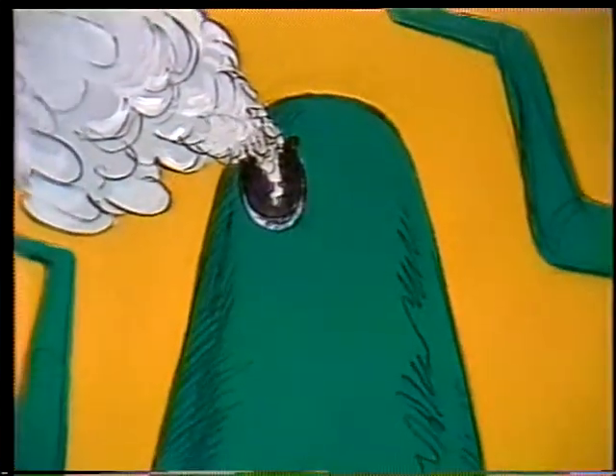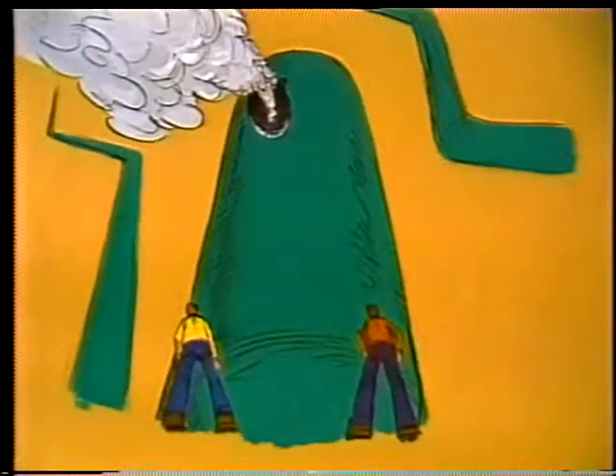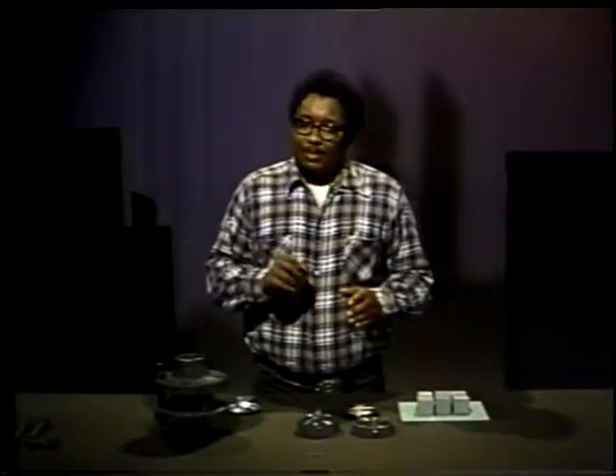No matter what type of rupture disc is used, the principle is the same. The disc forms a weak spot in the system, saving other parts of the system from pressure damage. And if a rupture disc is placed well away from heavily traveled areas and normal work areas, it also relieves excess pressure safely, away from workers and other equipment. If a rupture disc must be used where workers normally are, it can be connected to discharge piping, which will safely carry the pressurized fluid away when the disc ruptures.